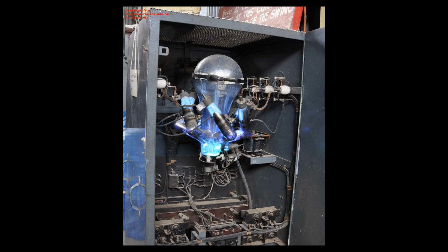However, starting about 1975, silicon devices have made mercury-arc rectifiers largely obsolete, even in HVDC applications. The largest ever mercury-arc rectifiers, built by English Electric, were rated at 150 kV, 1800A, and were used until 2004 at the Nelson River DC Transmission System High Voltage DC Power Transmission Project. The valves for the Inter-Island and Kingsnorth projects used 4 anode columns in parallel, while those of the Nelson River project used 6 anode columns in parallel in order to obtain the necessary current rating.